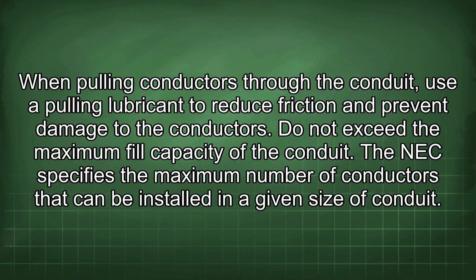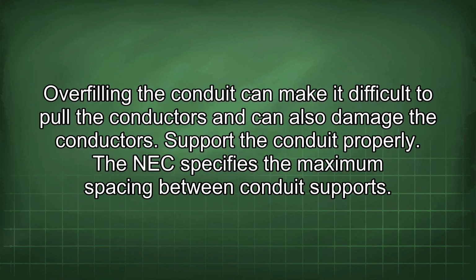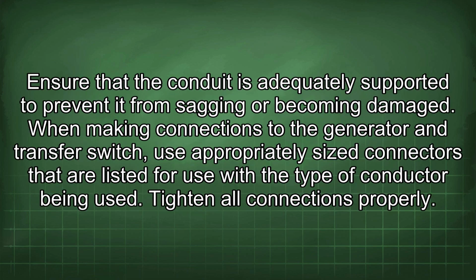The NEC specifies the maximum number of conductors that can be installed in a given size of conduit. Overfilling the conduit can make it difficult to pull the conductors and can also damage the conductors. Support the conduit properly. The NEC specifies the maximum spacing between conduit supports. Ensure that the conduit is adequately supported to prevent it from sagging or becoming damaged.